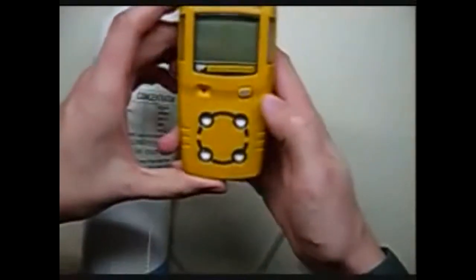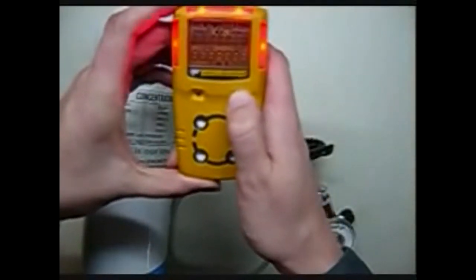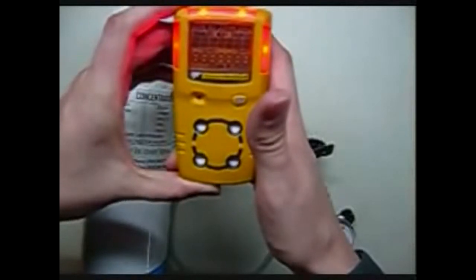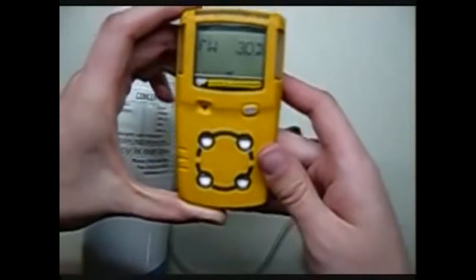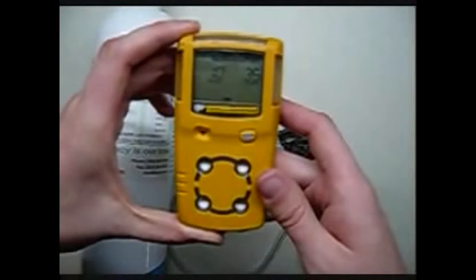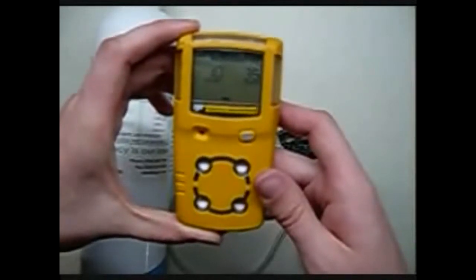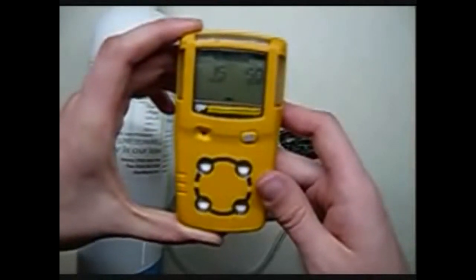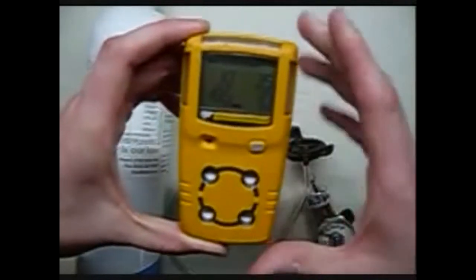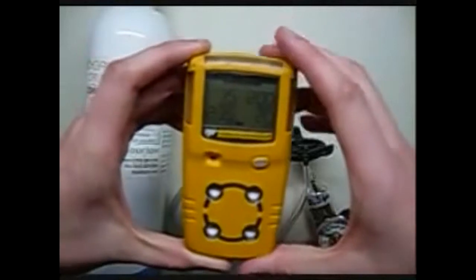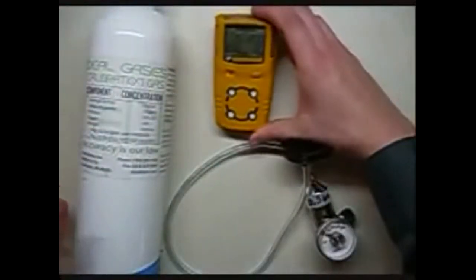In order to turn it on, hold down the button on the front until it beeps, then release. It'll run through a self-check, give the alarm set points, your TWA and your STEL, as well as your low and high alarms. Okay, put that down and let it finish.